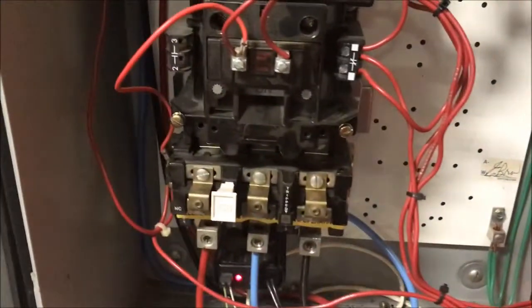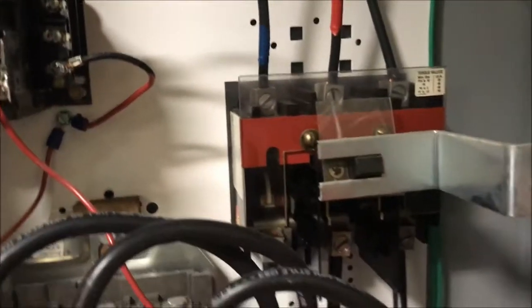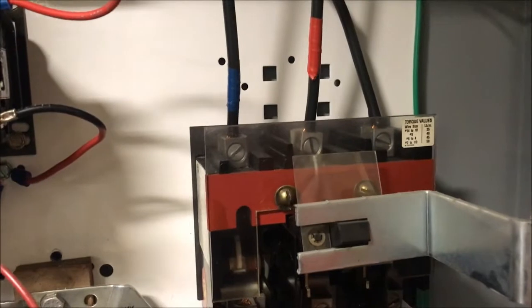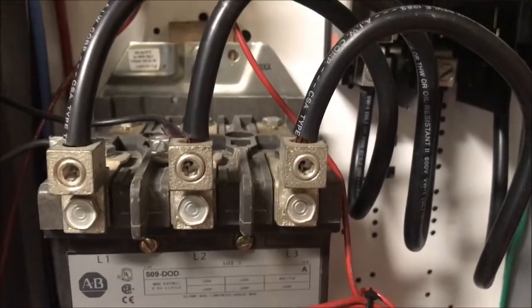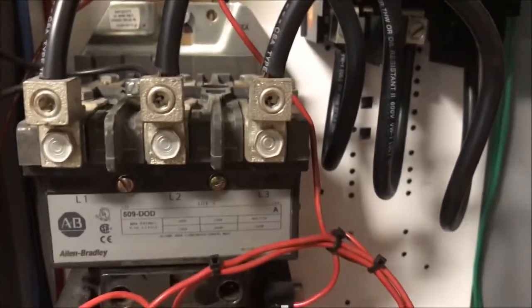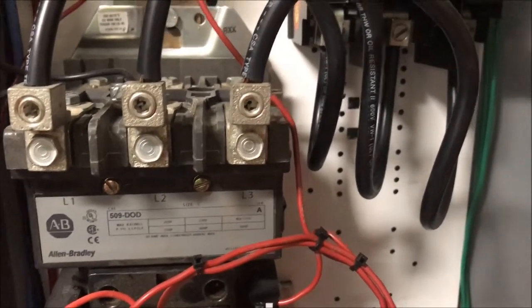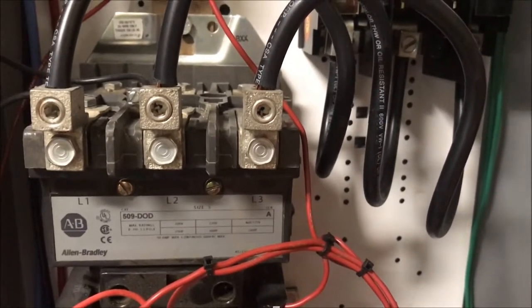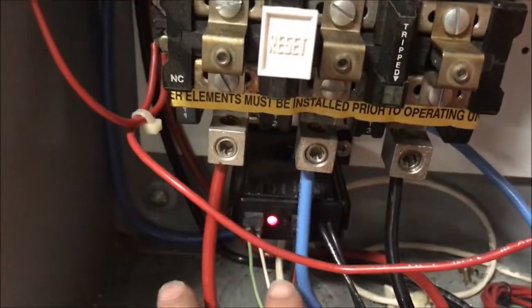Now I checked rotation on the panel, and I had counterclockwise rotation from L1 to L3. So in my mind, I was thinking most motors, when you look at the shaft end, run clockwise normally, and that's the rotation I needed. So I thought I'd have to swap these 2 wires.